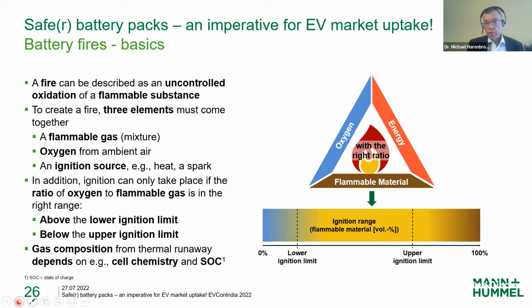One additional point, as I mentioned, battery fires are very important. Let's go back a little to the basics. How can battery fires take place? You can call a fire an uncontrolled oxidation of a flammable substance. So you need three elements to create a fire: a flammable gas mixture, oxygen from ambient air, and an ignition source.